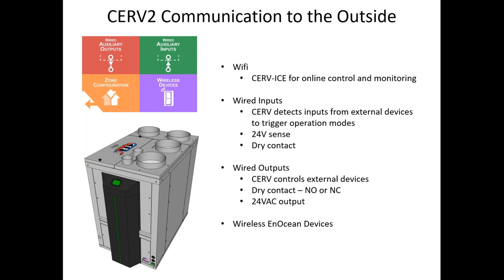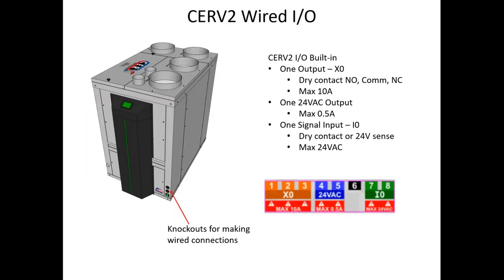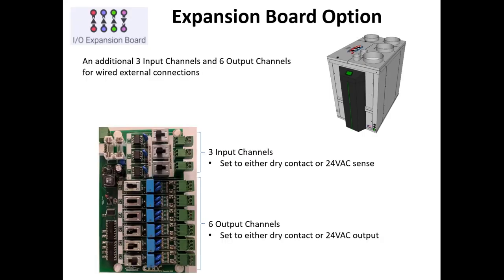Other communication to the outside: there's Wi-Fi, and then there's wired inputs and wired outputs, and then the wireless local EnOcean devices. The inputs are things where the CERV detects an input from an external device to trigger operation to occur. And then outputs are where the CERV is sending a signal to something externally to turn it on or off. The CERV standard has one input and one output built into it. So there's dry contact or 24 volt output, and then a dry contact or 24 volt sense on the inputs. To expand beyond that, you can add three input channels and six output channels through our expansion board. These are all wired to the CERV itself.